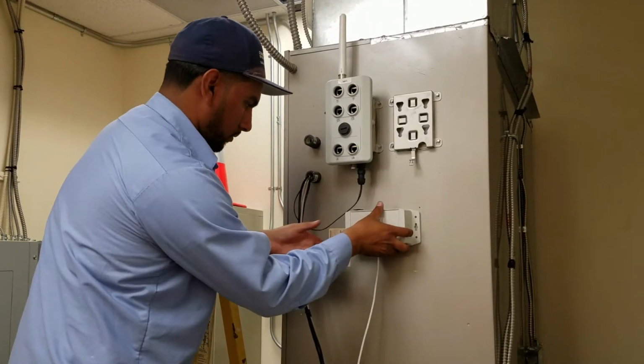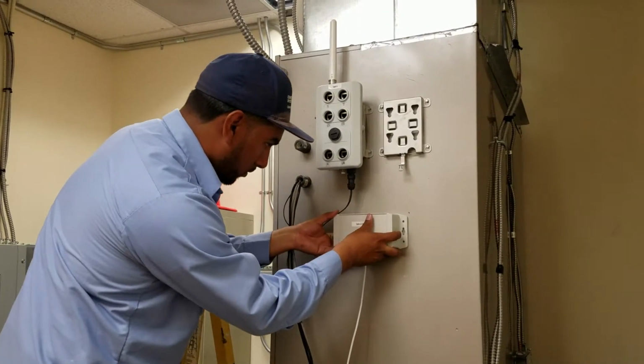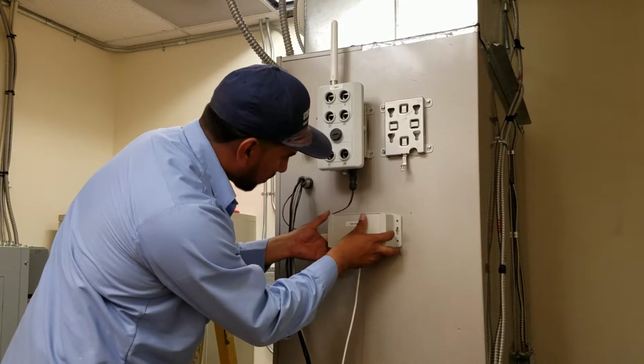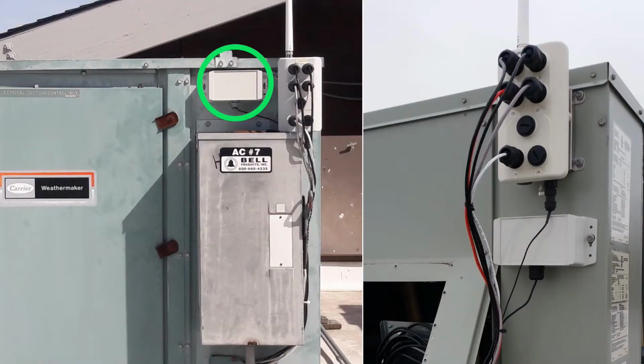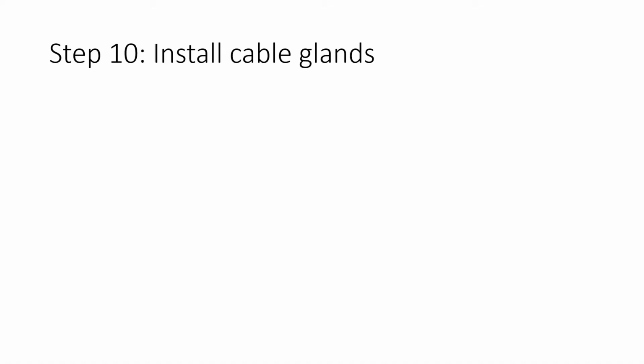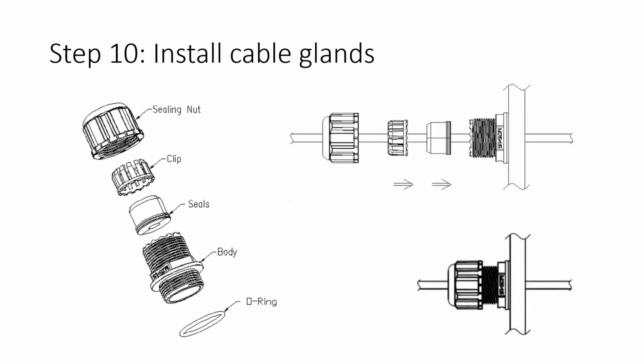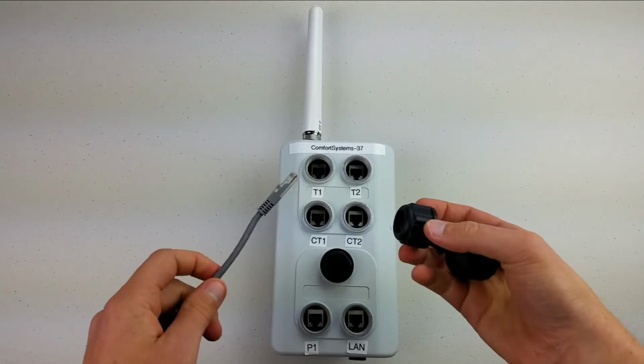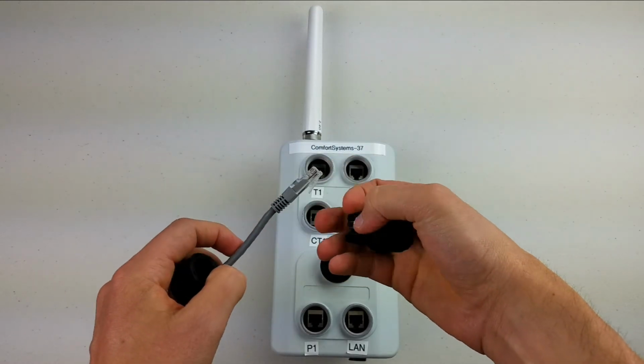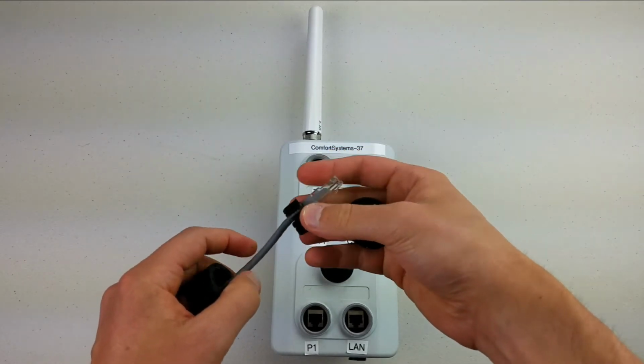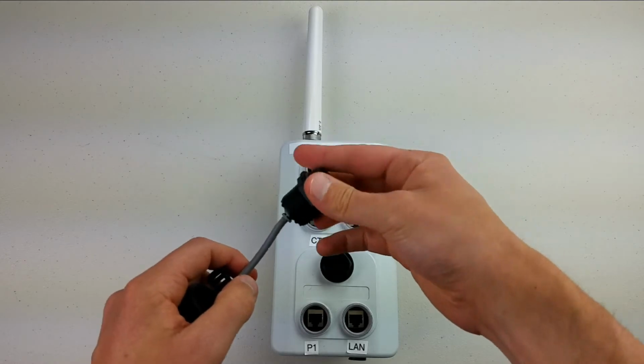Step 9. Install modem and modem case. Find the location that you identified in Step 4. Using self-tapping screws, fasten the modem case onto the exterior of the HVAC unit. If this unit does not require a modem, skip this step. Step 10. Install cable glands on sensor cables. Disassemble gland and thread the sealing nut, clip, body, and O-ring onto sensor wire.